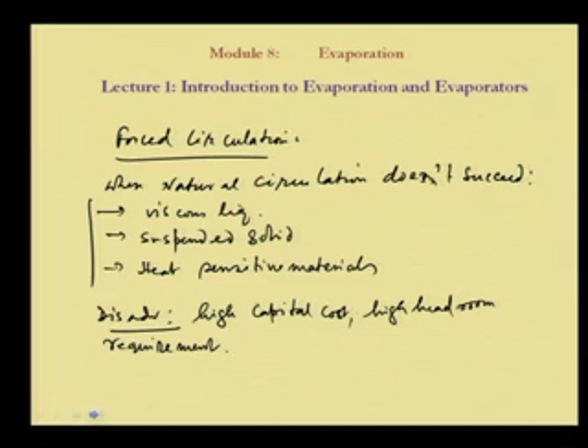This high headroom requirement is for cases where the fluid is not allowed to boil in the tube, and it is taken to the vapor flashing zone, in the headroom, where the pressure is reduced, the volume is increased, and the temperature will be less, so the liquid can flash over there. To accommodate the flashing vapor, high headroom is needed.